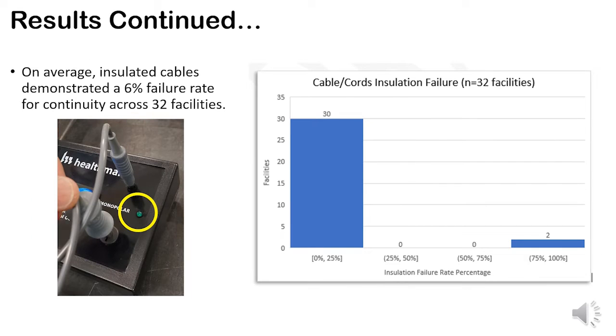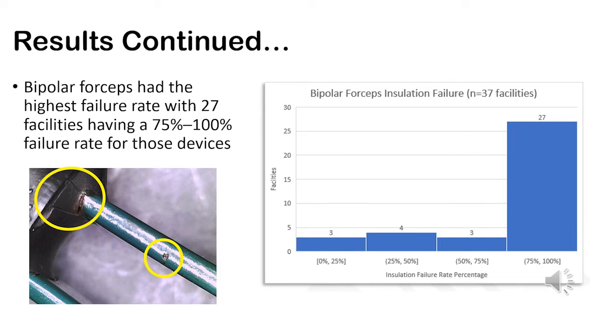On average, insulated cables demonstrated a 6% fail rate for continuity across 32 facilities. Even though it's only 6%, it only takes one to cause an OR fire, which, if you don't know, in the FDA MAUDE reporting database system, there were a lot of fires and burns attributed to monopolar cords. Bipolar forceps had the highest fail rate, with 27 facilities having a 75 to 100% failure rate for those devices.